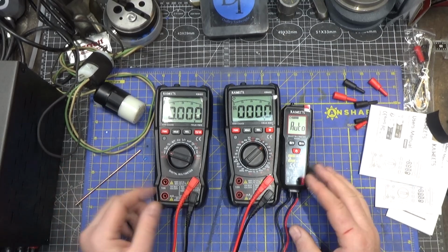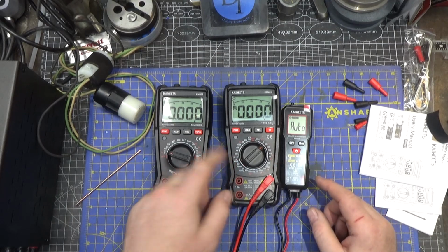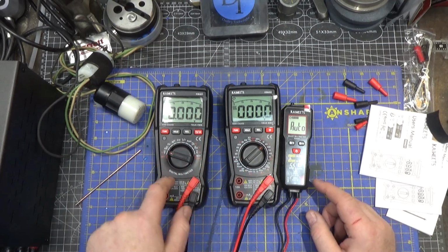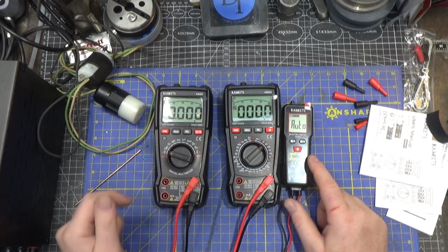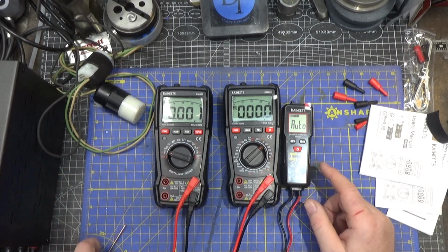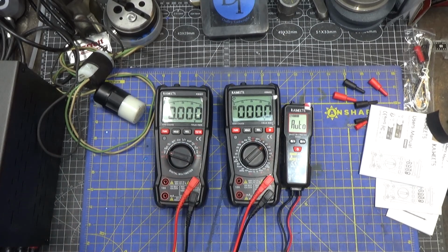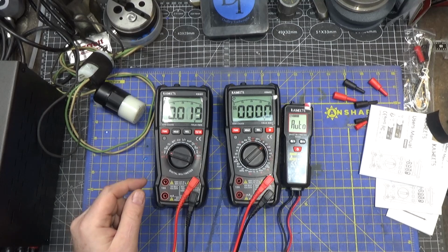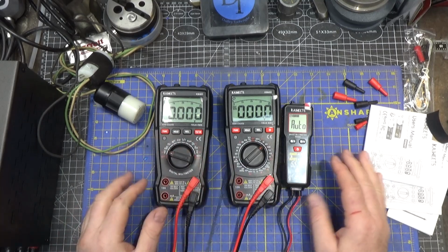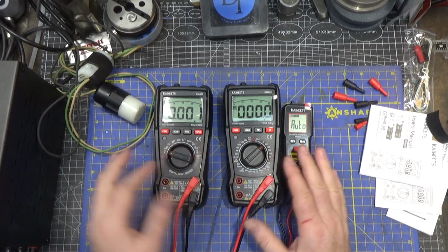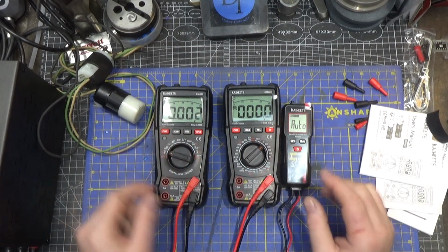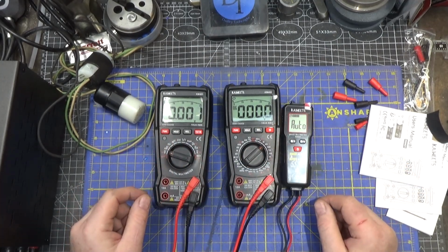The live testing sort of worked on this one, didn't work on this one, and didn't really work on that one either. So I think those are gimmicks. Don't rely on it. Get your probes on there and measure the voltage to be safe, especially if you're going to get your hands on that circuit. Don't trust the non-contact voltage measurement on any of these. I would take the probes and double check. Other than that, the accuracy is good.